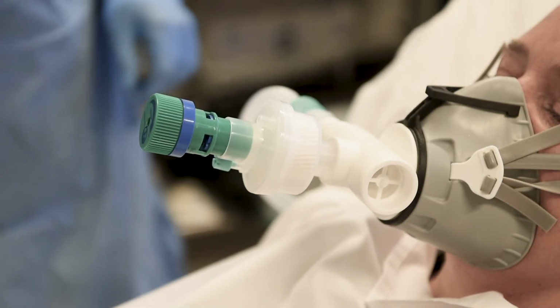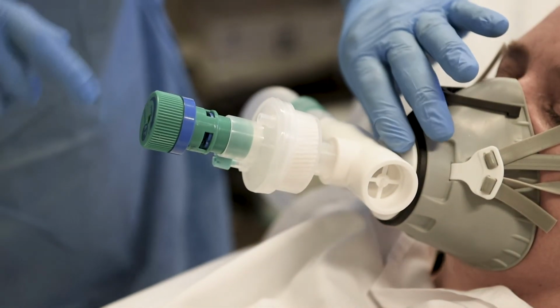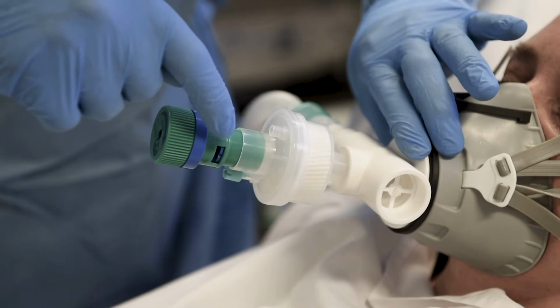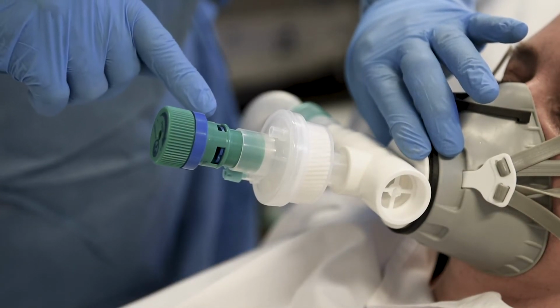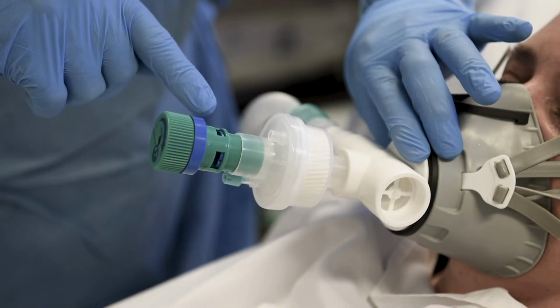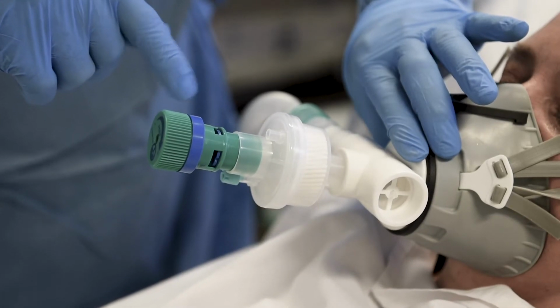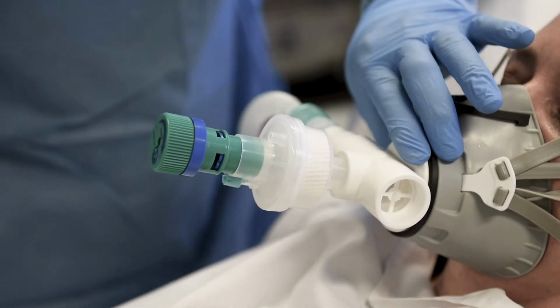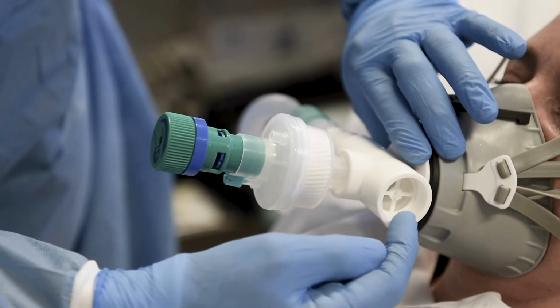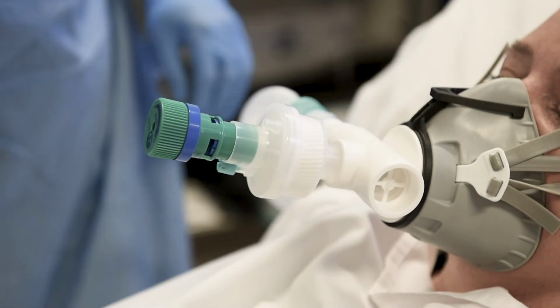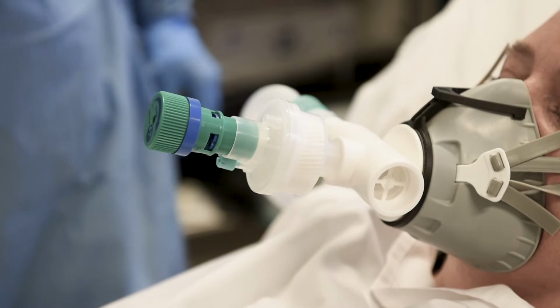Having done that, you need to make some checks on the mask itself. Look at the PEEP valve and make sure that there's gas escaping from the PEEP valve, especially when the patient breathes out. On the side of the mask, there's another valve, and this is an emergency valve if there isn't enough gas being supplied to the patient.